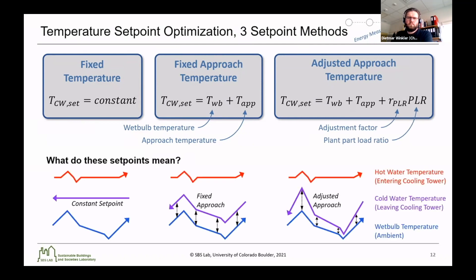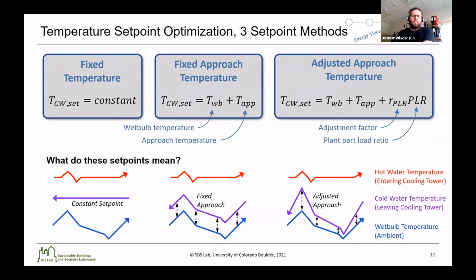For cooling towers, there's hot water entering the cooling tower, and the cold water leaving the cooling tower is at some value lower than the hot water but above the ambient wet bulb temperature. For the fixed temperature method, this leaving cold water temperature is controlled at a constant setpoint. For the fixed approach temperature, the offset from the wet bulb temperature is always constant. And for the adjusted approach temperature, that offset from the wet bulb is changed depending on the part load ratio. All of these implementations are seen in practice; the fixed temperature is very common and simple. However, there are many benefits to the approach temperature methods that often provide additional cooling energy efficiency.